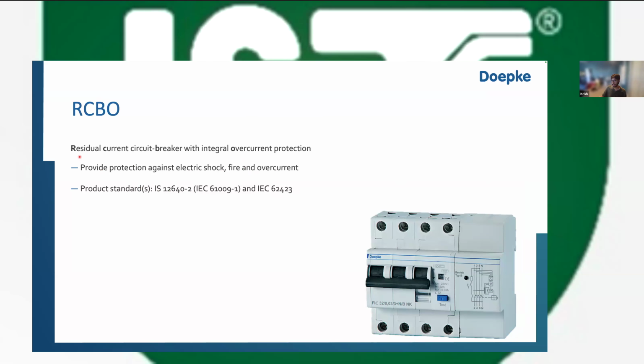The RCBO is a residual current circuit breaker with integral overcurrent protection. This is a device that provides protection against electric shock, fire, and overcurrent as well. Think about it simply, an RCBO is like an RCCB plus an MCB combined in one. Its product standard is IS 12640 Part 2, which is an adaptation of IEC 61009 Part 1 and IEC 62423. So this is like an MCB plus RCCB, and this is just the RCCB. Obviously, now you have a much more compact version. This is a very old picture just taken for illustrations.